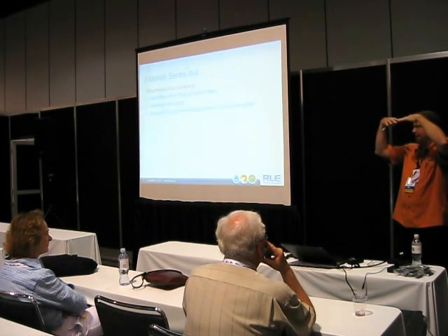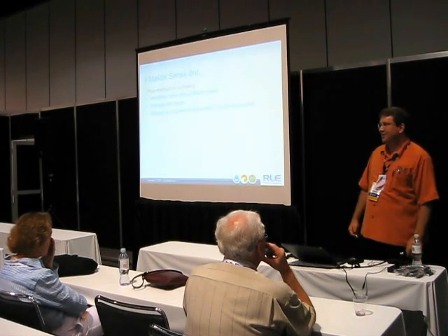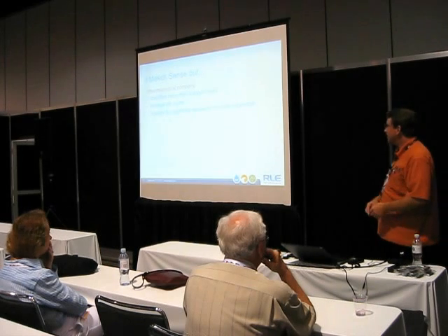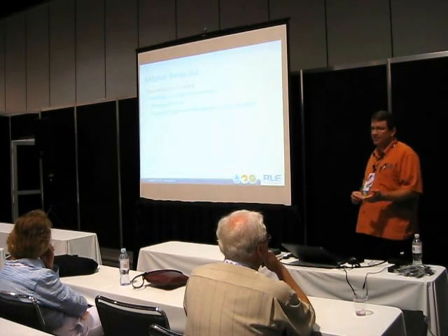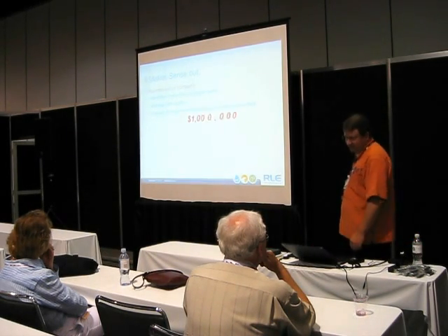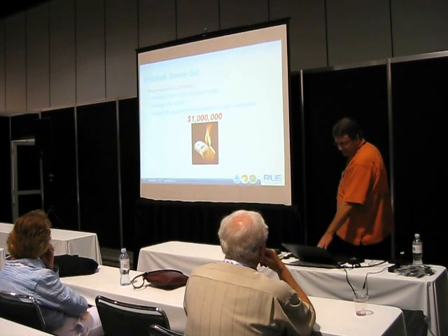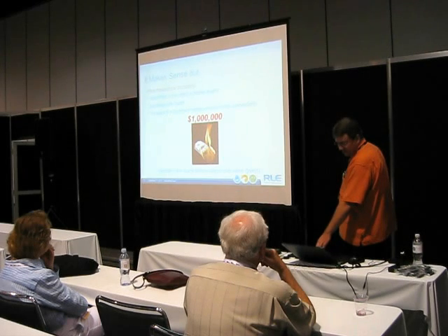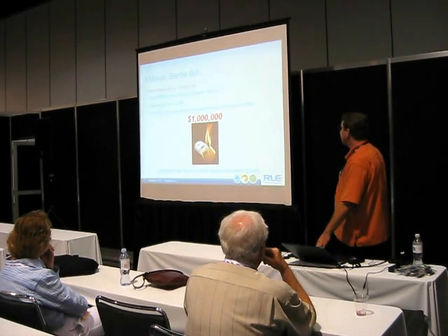ended up rupturing, and it started sagging on the tile. It was dripping through the tile a little bit, and the timing was such that he looked up and that tile gave way and it all came down on top of him. Like I say, sometimes the truth is better than fiction. So we ended up putting a very comprehensive system in there, wrapping pipes again, incorporating distributed leak detection, one technology we'll talk a little bit about. But when that initial equipment was damaged, it was over $1 million, as I mentioned. And before that, we had that other line burst before final approvals were given.